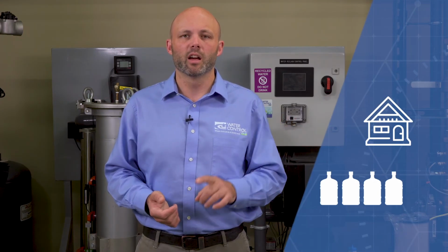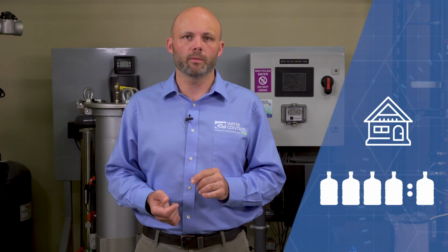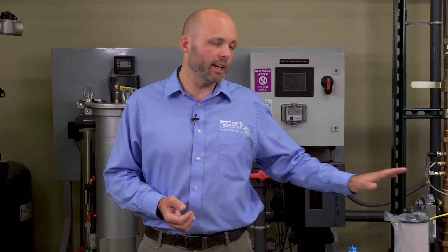Most residential systems create 3 or 4 gallons of concentrate for every 1 gallon of permeate generated. Commercial systems, on the other hand, are usually 1-to-1 permeate to concentrate due to the pumps involved. These two streams of water perform a process that we call cross-flow filtration. In a word, the filter is constantly being flushed, giving it a much longer lifespan than normal flow-through filters. Sometimes water produced with reverse osmosis is further purified using deionization media. In general, though, we can achieve about a 96 to 99% reduction in levels of dissolved solids using RO alone.